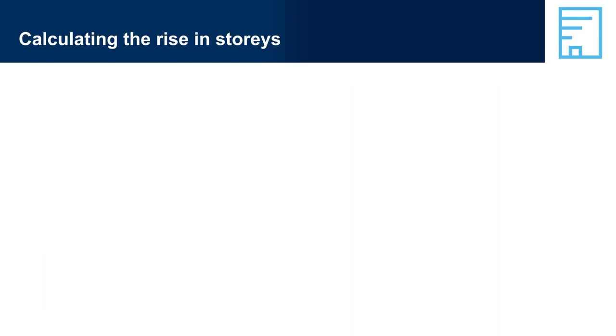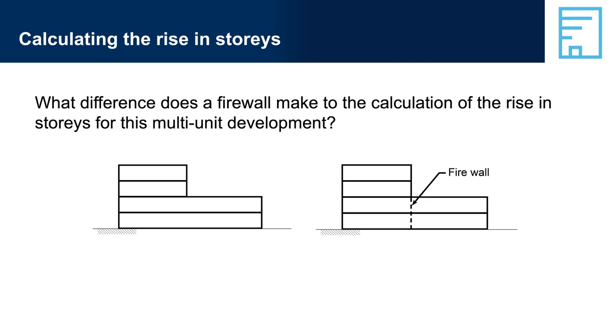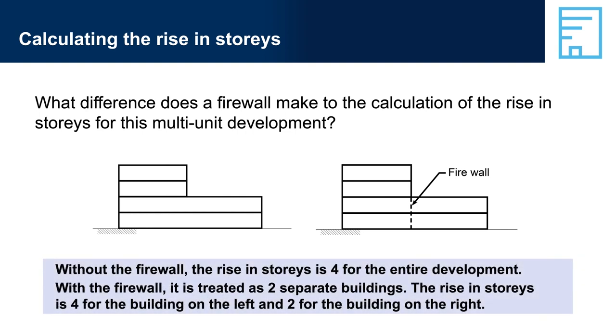Calculating the rise in stories: What difference does a firewall make to the calculation of the rise in stories for this multi-unit development? Without the firewall, the rise in stories is four for the entire development — the two-storey section must also be built to meet the fire protection provisions that apply to the four-storey section. With the firewall, the rise in stories is four for the left section and two for the right section, so the provisions that would apply to each section are potentially different. This doesn't mean that the builder would automatically build the two sections to different standards.